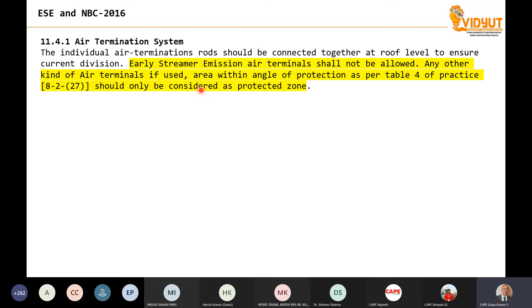Air termination system: the draft says early streamer emission air terminals shall not be allowed. Any other kind of air terminal, if used, area within the angle of protection as per table 4 of the practice shall be considered as protected zone. So indirectly, what it says is, if you have a rod for lightning protection, we are supposed to consider that the area within the angle of protection is the protected place. Even if you use an ESE rod, you should consider the angle of protection and use it. This is the recommendation in the draft.